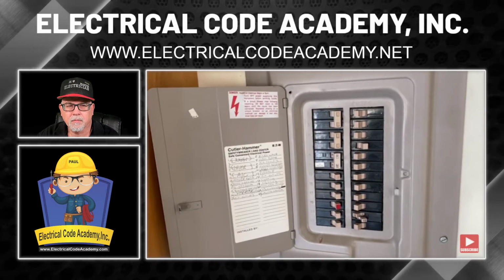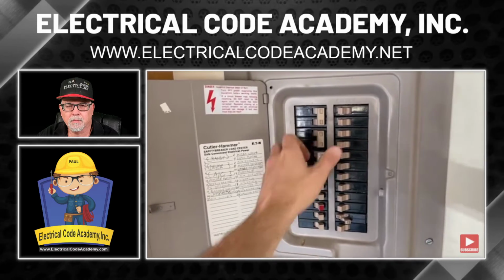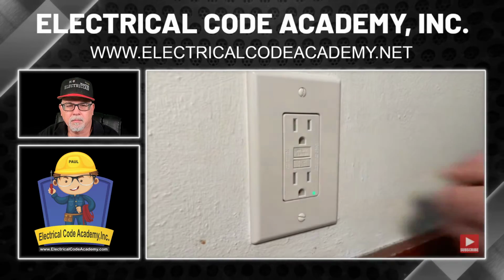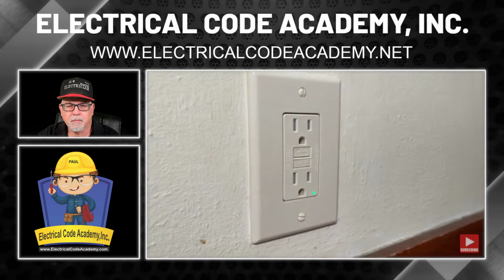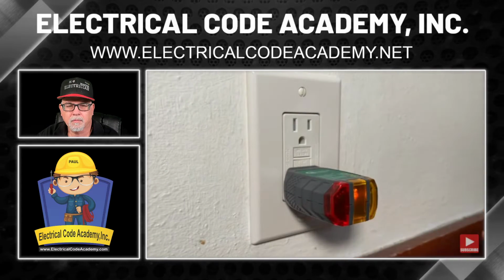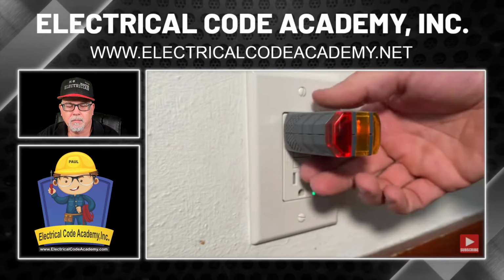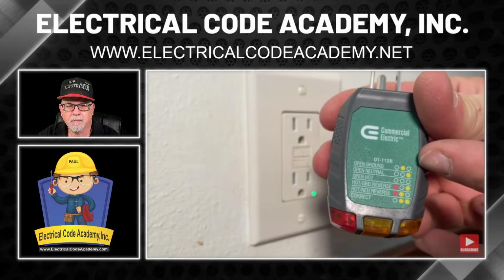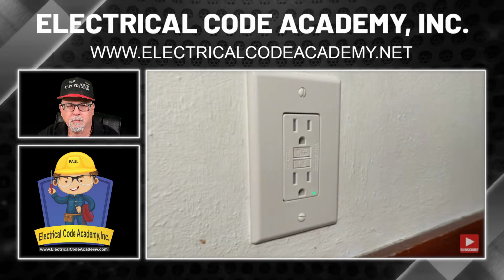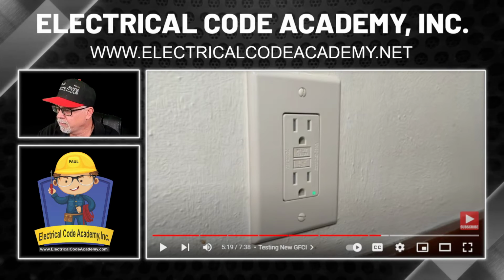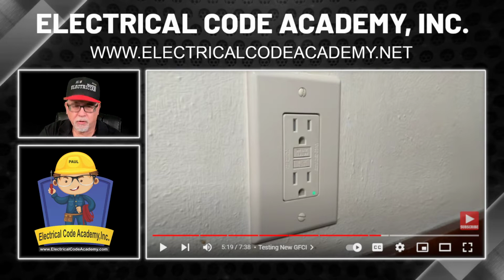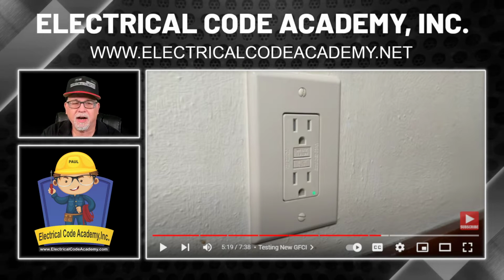So go hit your breaker back to the on position. And we'll press the reset button, testing with our voltage tester. Everything looks good. I'll also use an outlet tester where I only have the center LED on, which does mean open ground, which is expected. Okay, all that's true. I would expect an open ground because there's no ground there, obviously.